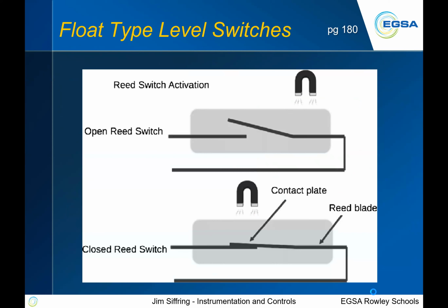Float type switches, real common in a float switch are reed switches. I'll show you an example after we look at this, but a reed switch is basically a switch inside of a glass vial, and this little thing is less than a quarter inch around. They're small, skinny glass vials, and in the presence of a magnet, they'll close or open, change state, whatever that happens to be, just like the graphic shows. So as you move the magnet closer to the switch itself, it may close, it may open. It's however that particular device is set up.